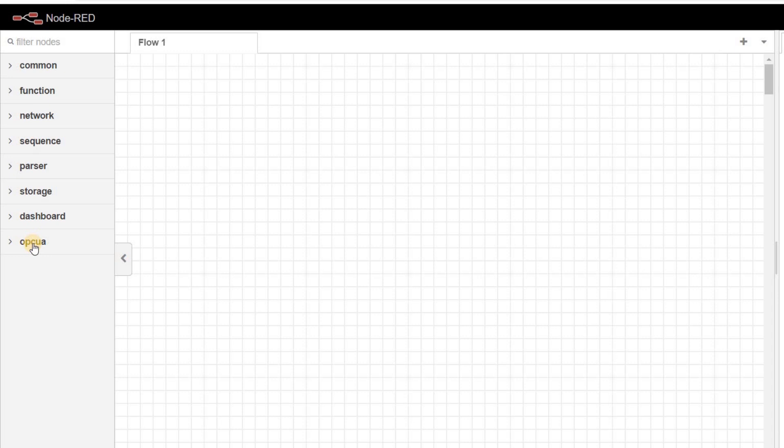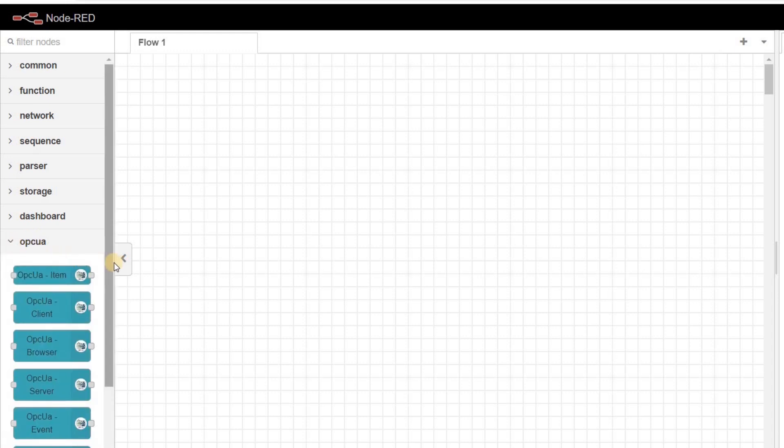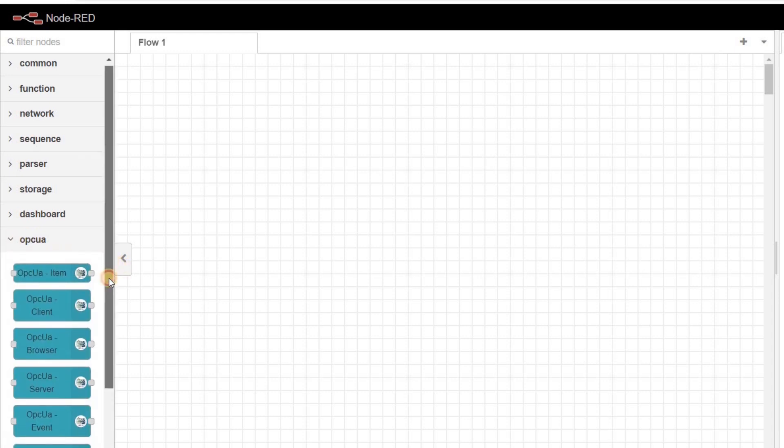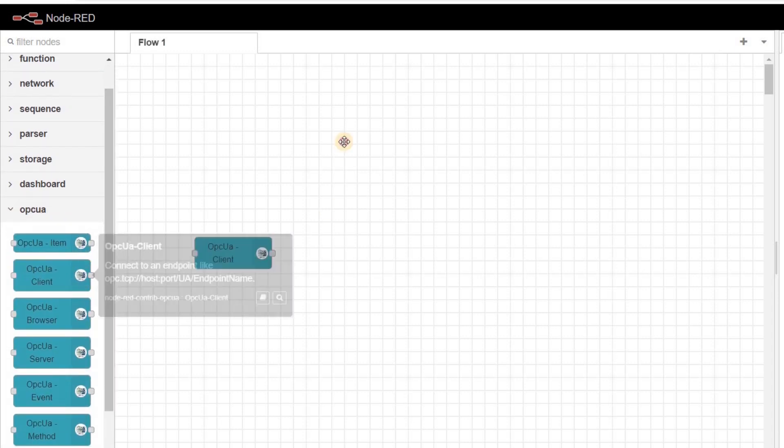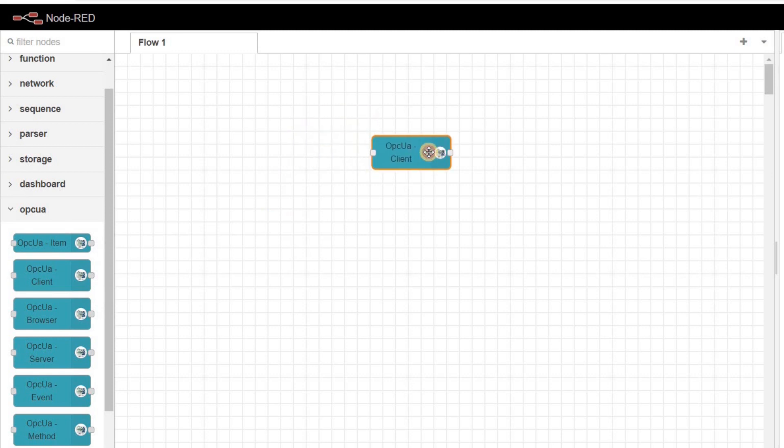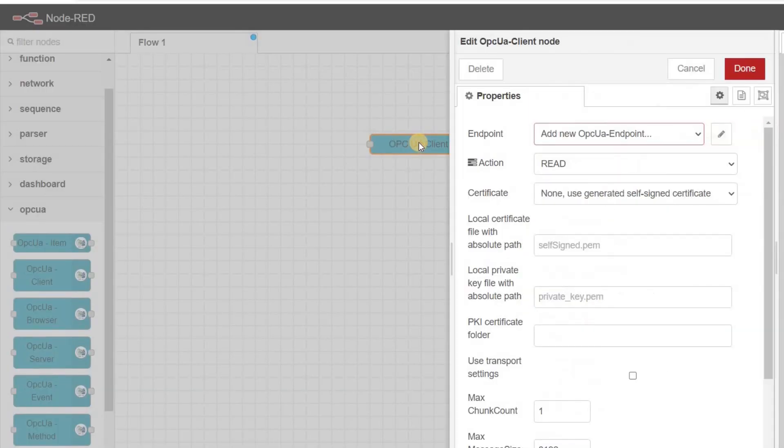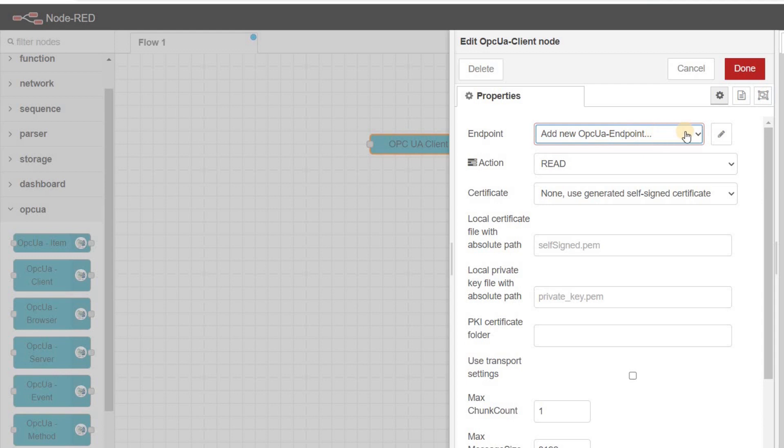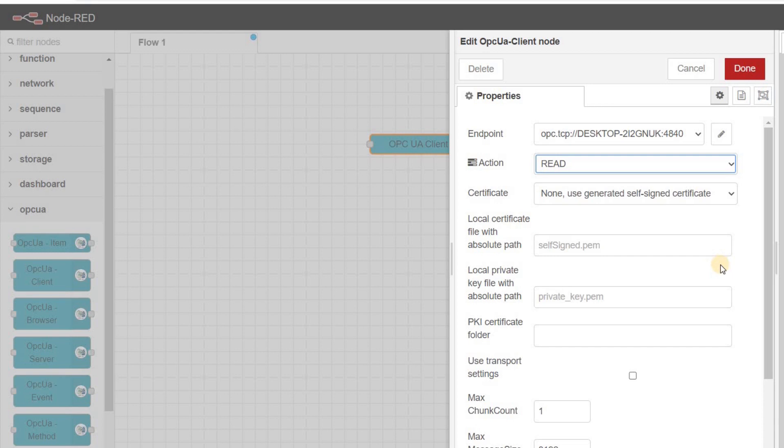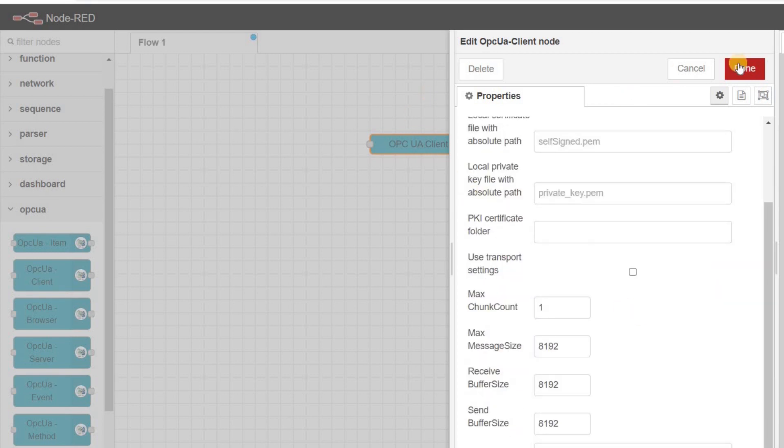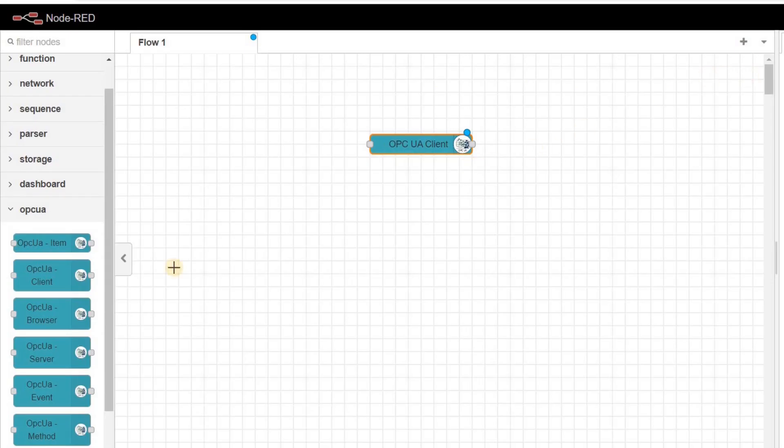In our flow in Node-RED, to set up OPC UA communication, we need to insert an OPC UA client node. In the properties of the node, endpoint is the address of the OPC UA server, and we choose read for the action, as we are going to read the value of a variable. We then need to add an OPC UA item node.